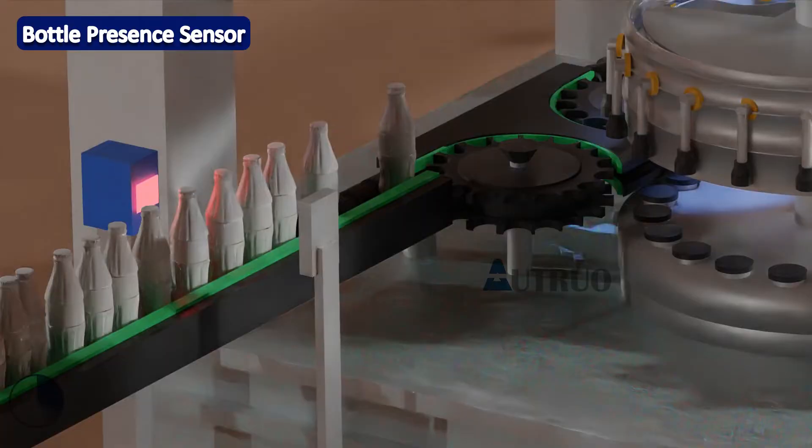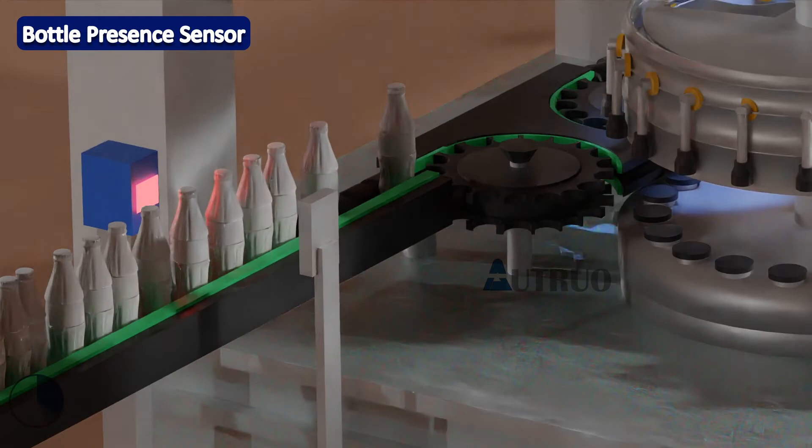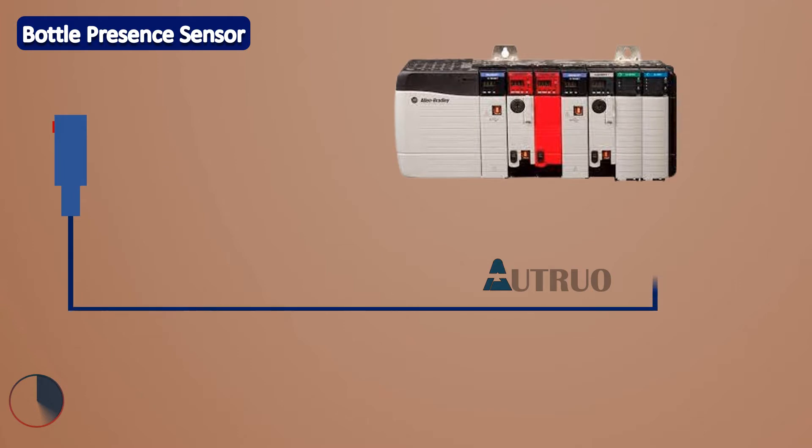At the infeed of the labeler lies an electronic sensor. This sensor is of different types, but the most common one is a photoelectric sensor. So basically, when the sensor detects the presence of a bottle at infeed, the sensor will send an electric signal to the PLC.